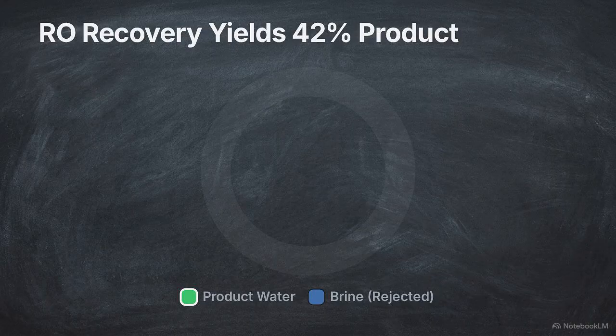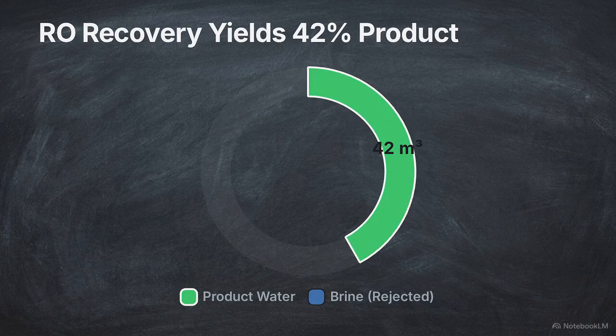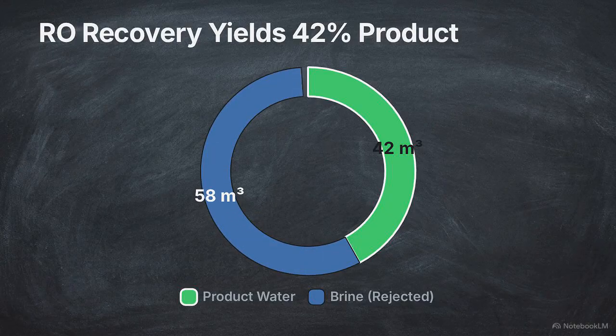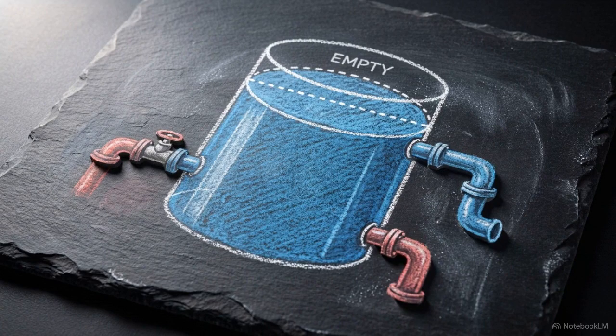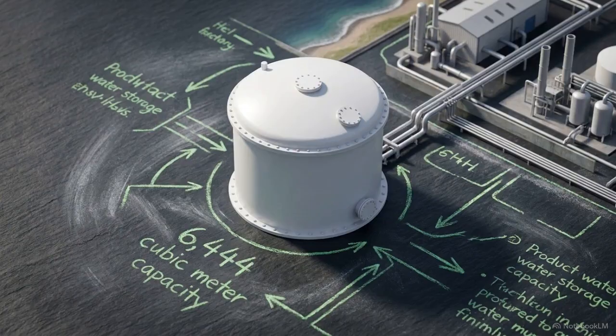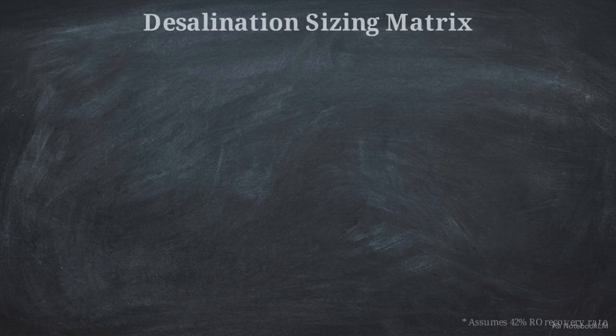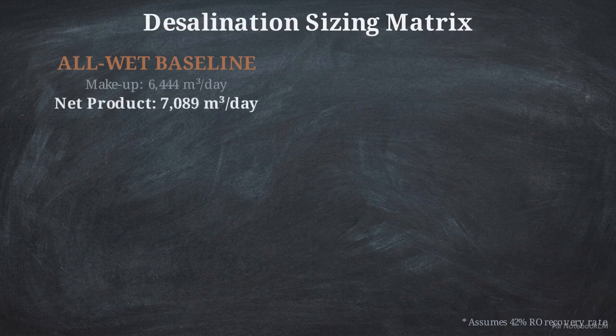The makeup water demand establishes the scale of the SWRO plant. Raw seawater is pulled through marine intakes, pre-treated, and forced through high-pressure membranes. The reverse osmosis recovery rate is 42%. For every 100 cubic meters of seawater processed, 42 cubic meters become product water, while 58 cubic meters are rejected as brine. We apply a 10% design margin to the tower's peak demand. For the all-wet closed baseline of 6,444 cubic meters, the SWRO plant must be sized to produce 7,089 cubic meters of net product. This sizing matrix shows the impact of cooling selection on the desalination infrastructure.